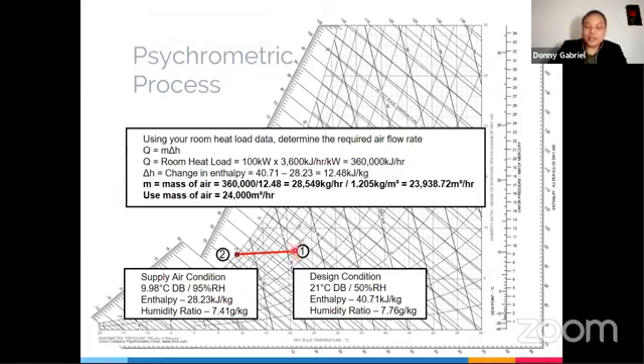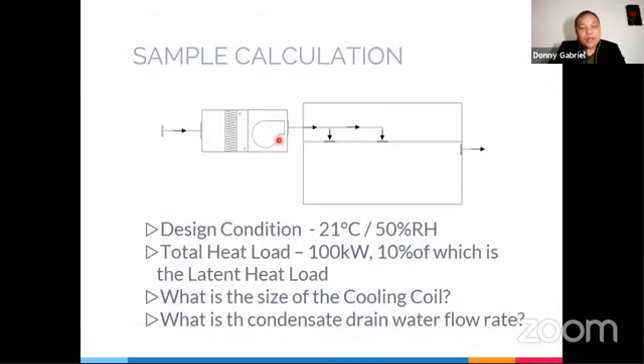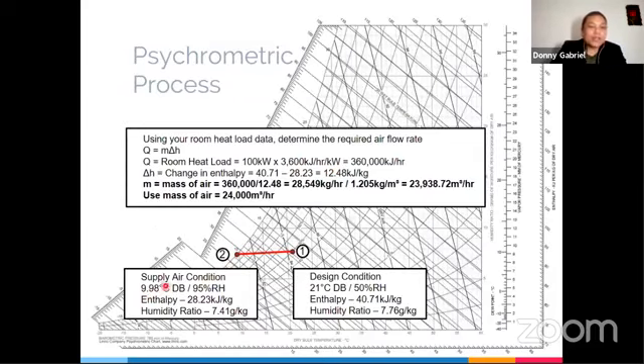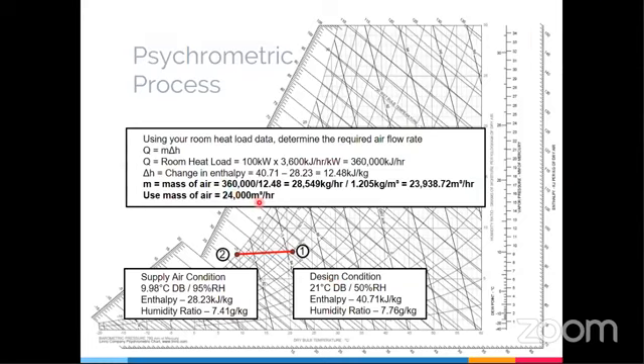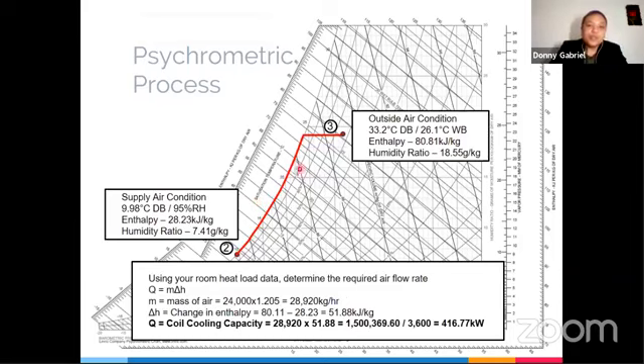Okay? So which means here in our schematic, you would need 24,000 air being pumped into the room so that it will cool down to 21 degrees Celsius, 50%. You need 24,000 cubic meter of air at 9.98 degrees Celsius to be inside the room, so it will cool down to 21 degrees Celsius. So now you already have your mass of air. Using this mass of air, you would need now to see how hard the coil needs to work. So from outdoor air to indoor air.